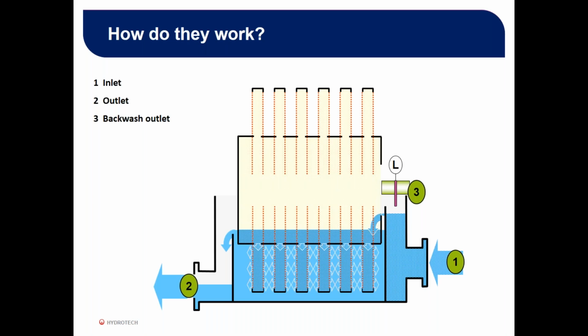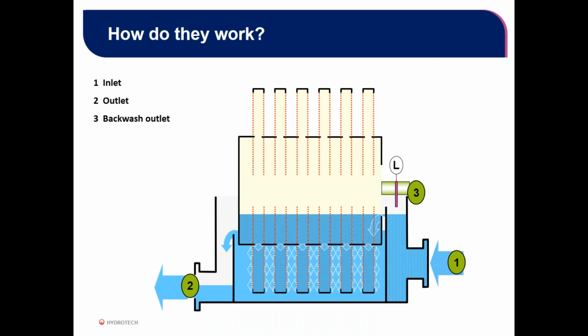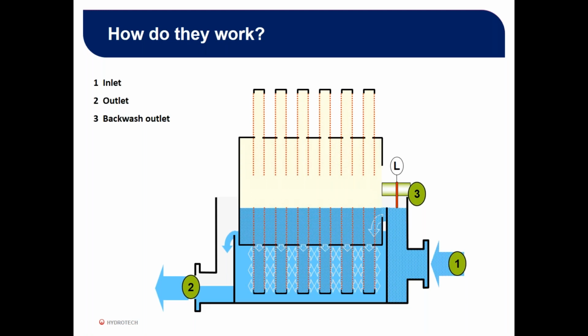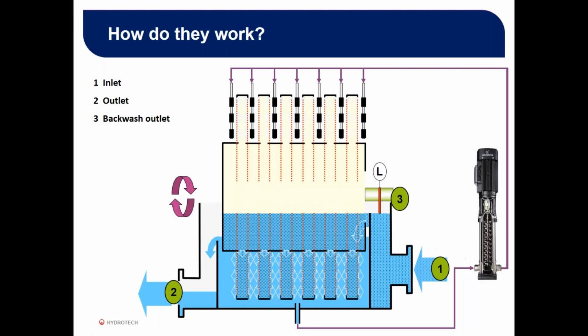And you can see as the solids begin to build up on the filter cloth as the water is going through it, it takes more and more pressure for the water to push through the filter cloth, and so the water level rises. When the water level rises to 250 millimeters, it triggers this level switch that you can see near number 3. And when the level switch triggers, it starts a backwash.